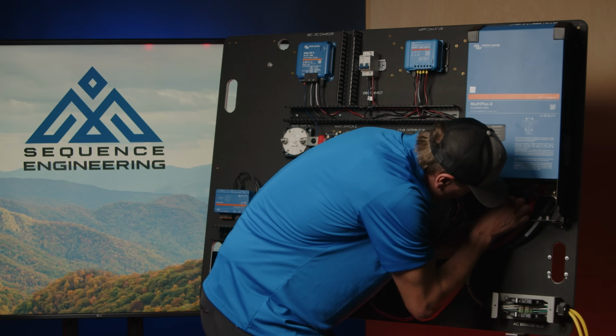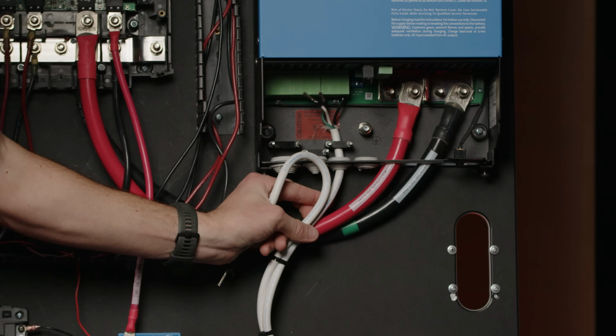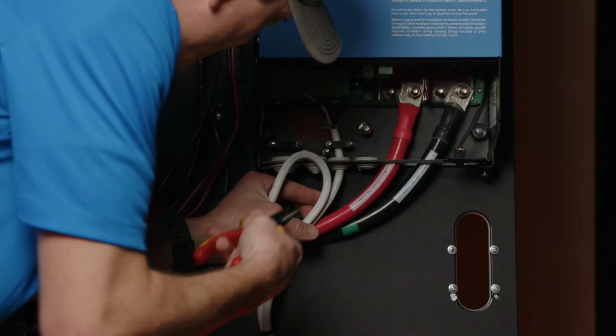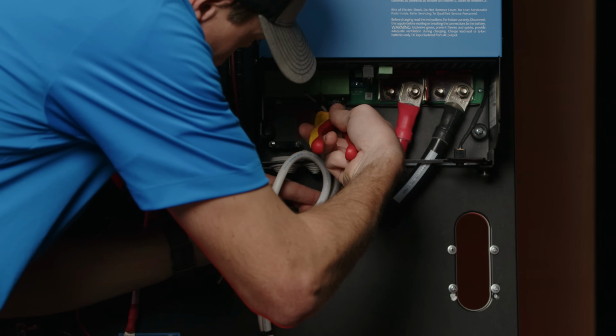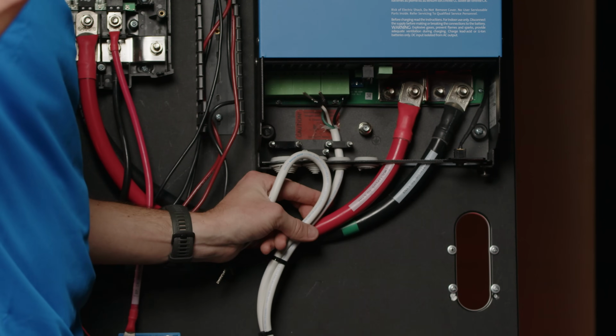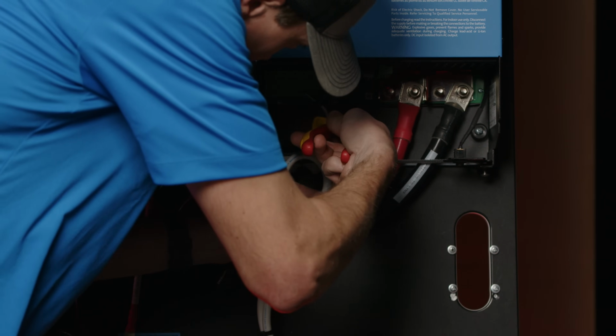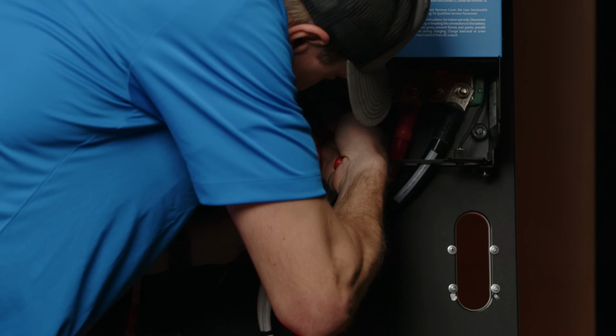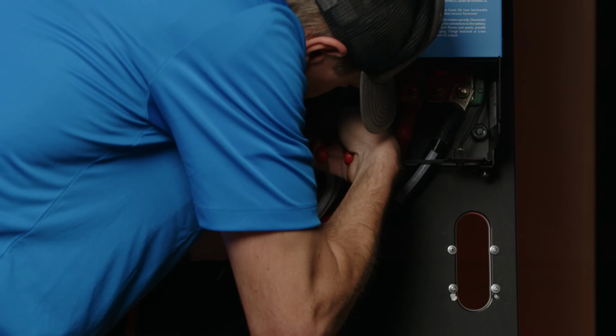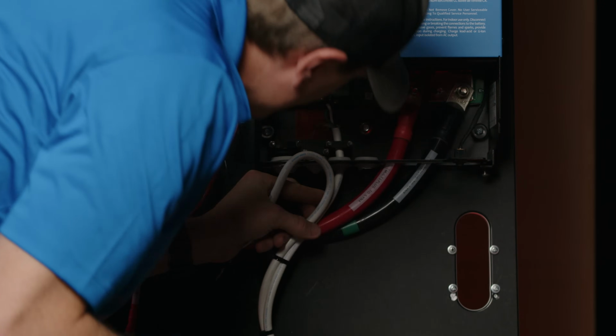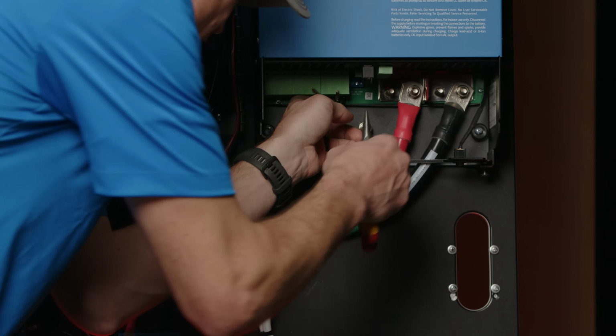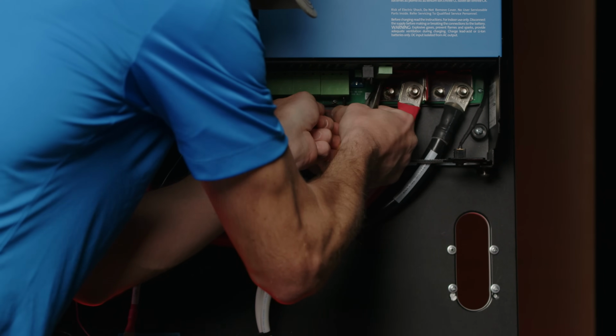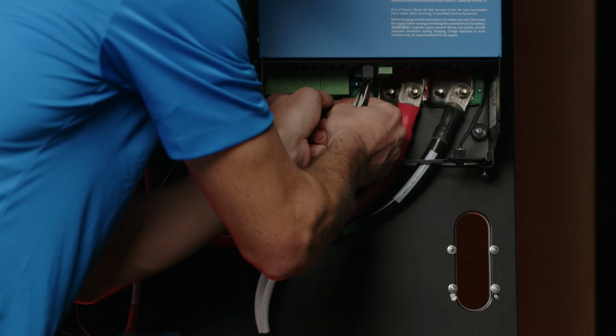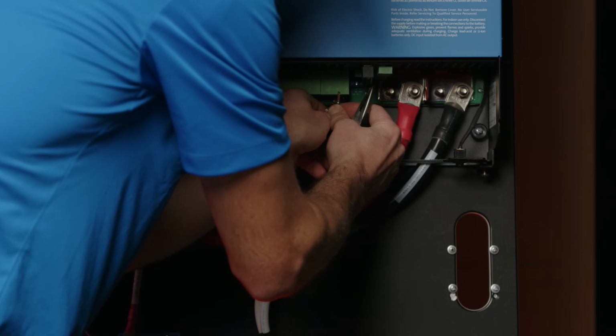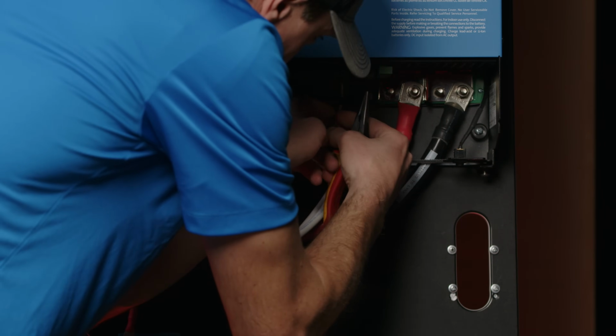I'll press that in there, and normally you get good engagement doing that. If you feel you need to push it in further, grab a standard set of needle nose pliers, grab the wire just below the ferrule, and make sure you've got full engagement. It went in slightly further, and I feel confident it's secure. I like to give it a tug just to make sure it's not going to come out or that I have a bad crimp on the ferrule.